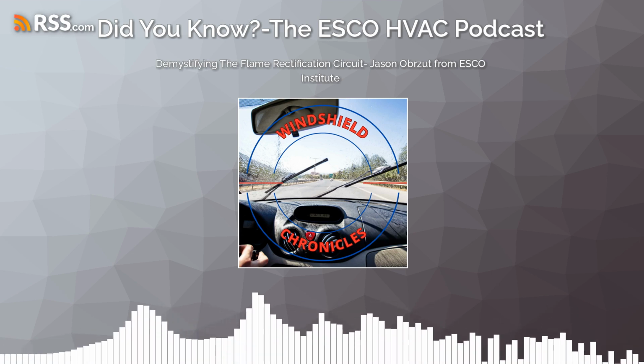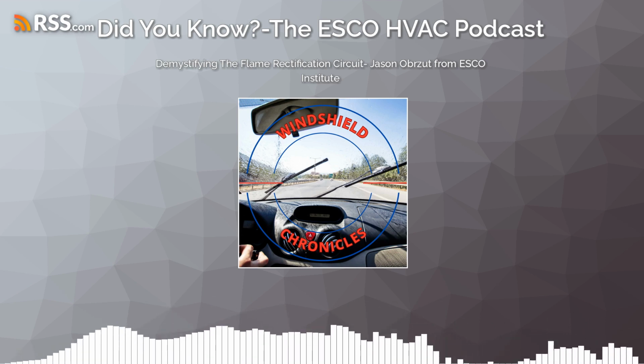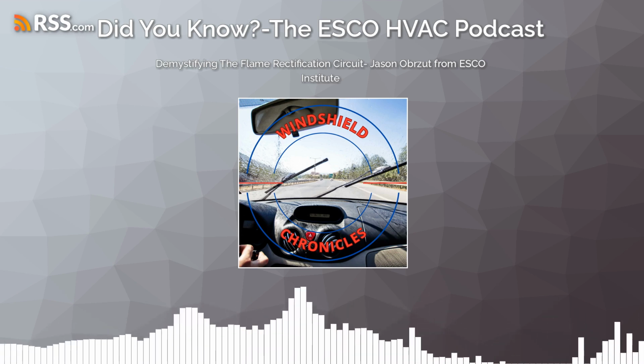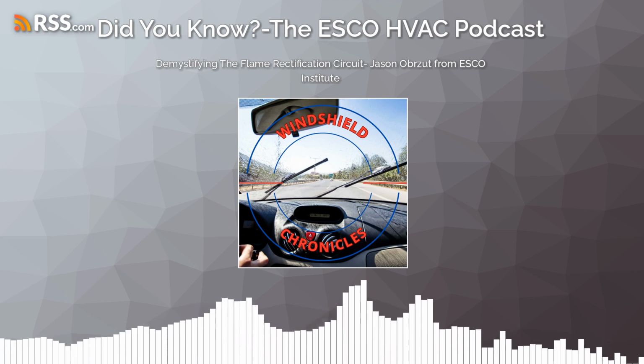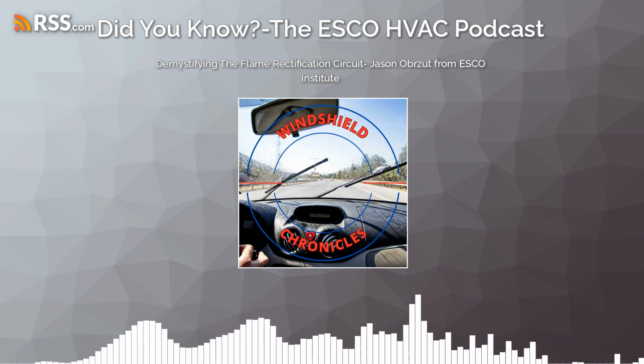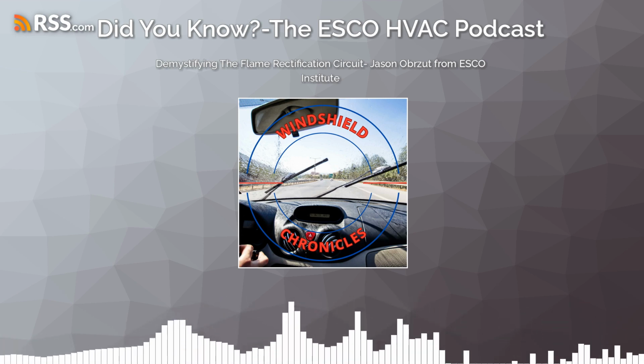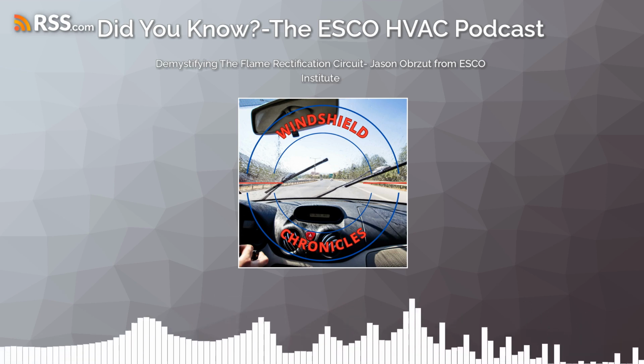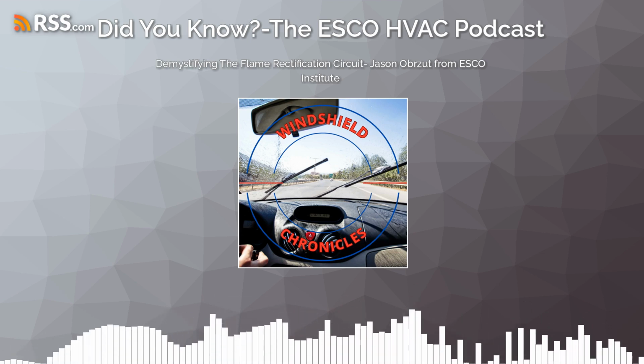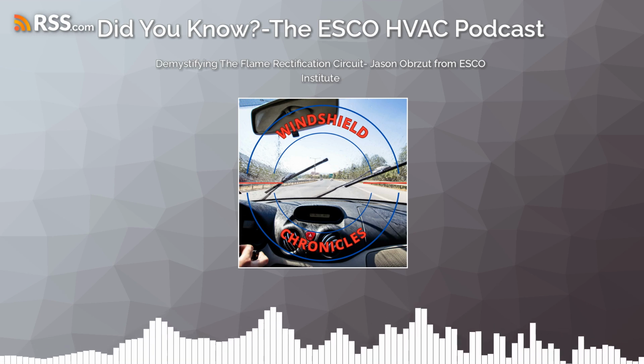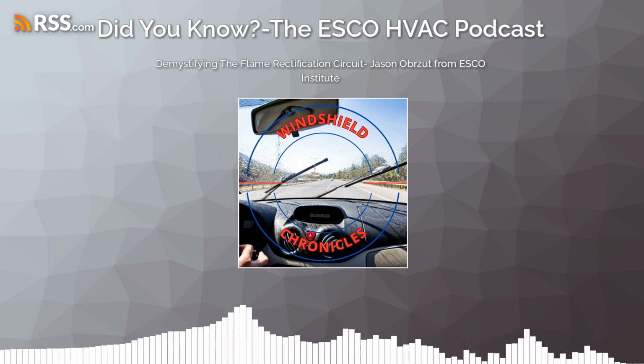Now I'll have a little bit of background noise as the blower and stuff kicks on, but I'm going to try to keep close to the microphone. I'll try and keep up with the speed of the board there. Yeah. As a board, once I receive this input signal from the thermostat, my reaction as a board is I'm going to send an output signal to the inducer motor. All right. Sounds the combustion blower, power venter, whatever they want to call it. It has a million names. There goes one.